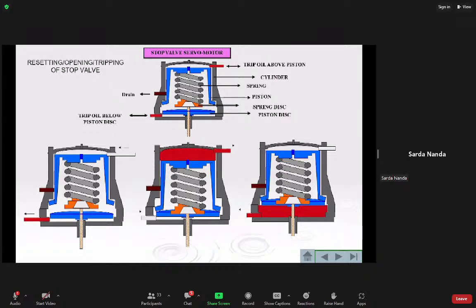It's all the same. In order to open the valve, I want trip oil pressure to go from here to push this bottom plate to the piston and open the valve. But if there is some place by which this entire oil can be drained, if there is a short circuit of oil through and the trip oil that comes over here gets drained from here, then there is no other option. Then your stop valve will not open at all. Your spring will not latch.